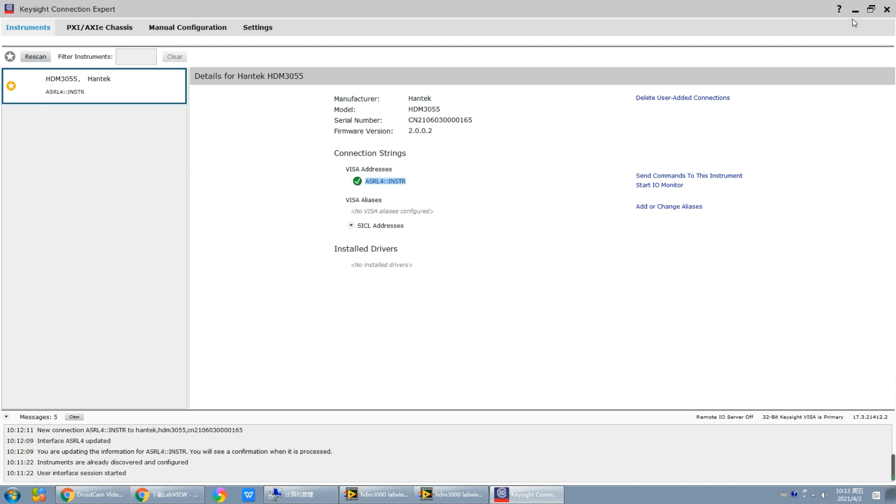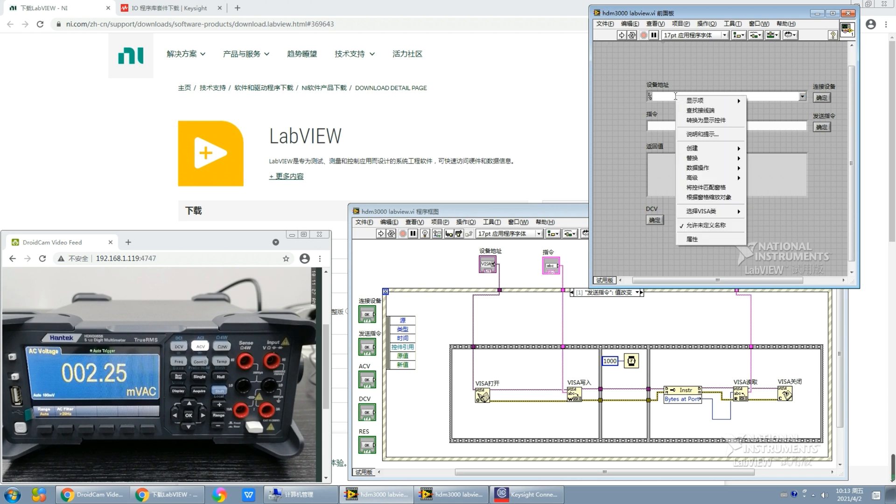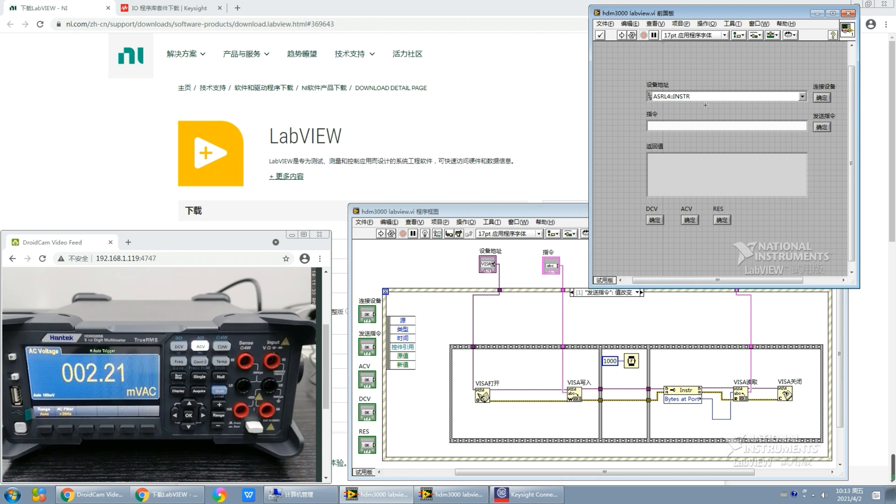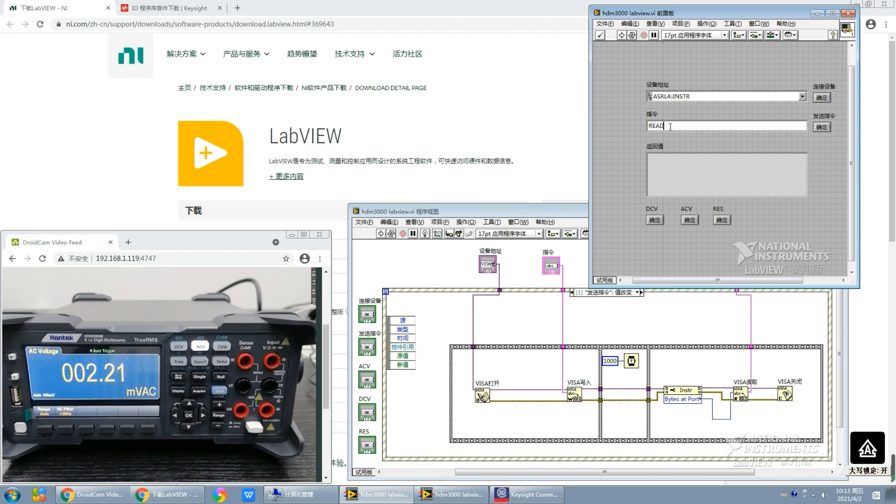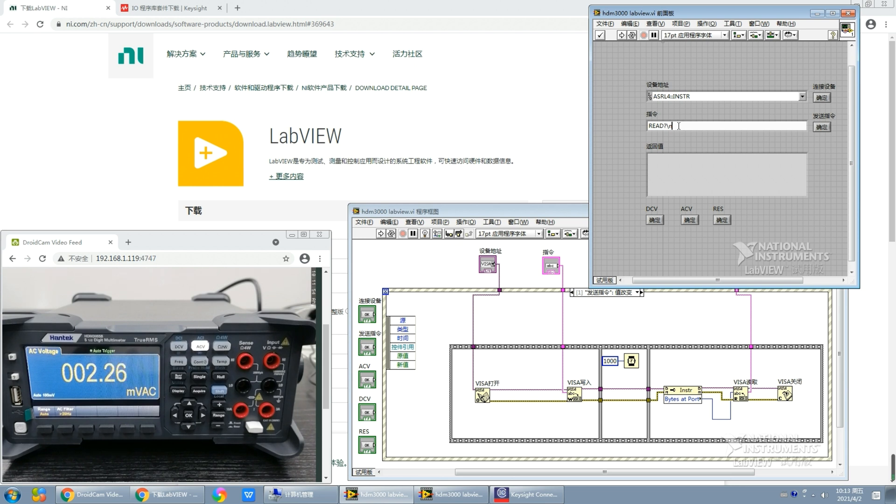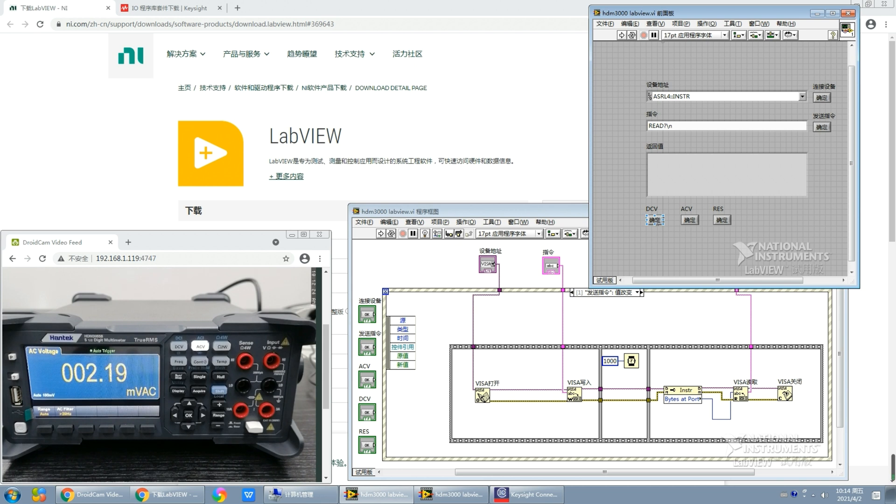Here we can input custom commands for the communication testing. Here we should input READ question mark backslash N. Please don't forget the backslash N because it is an end mark, and without it the program will not be executed correctly. After we send this read instruction, it will give us the current return value here. And here we can select the measurement functions, for example DCV, ACV, resistance, connectivity, and so on.